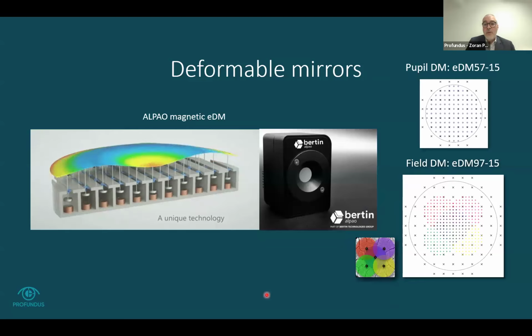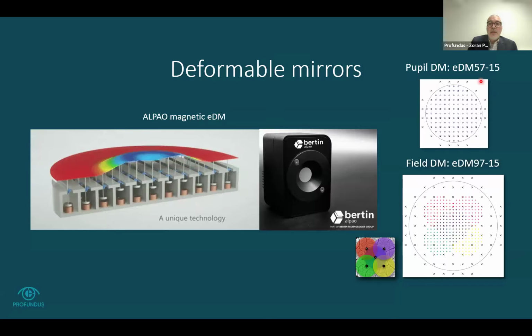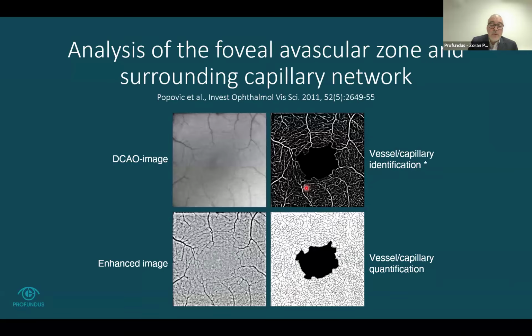And then we have 2 deformable mirrors from Alpao in our system. One pupil mirror, which is a converted 97. It's a 57 currently due to the optical design of our instrument. And we have a field deformable mirror, which is the DM 97 that takes care of field-dependent aberrations. If you remember the image I just showed you in the slide before with 5 colored areas on the retina with the beams covering that, that is basically the footprint of the beams that you will get on the field deformable mirror. So that is what we use to correct field-dependent aberrations. The pupil DM corrects pupil aberrations. And in the system that we're building, we are using the DMs from Alpao because of the advances of this technology. Like Julien just told you, there is no cabling now, there's no external electronics. So we were able to integrate all of this into one system.